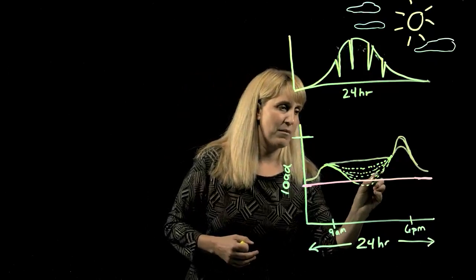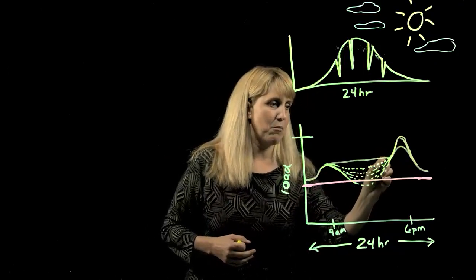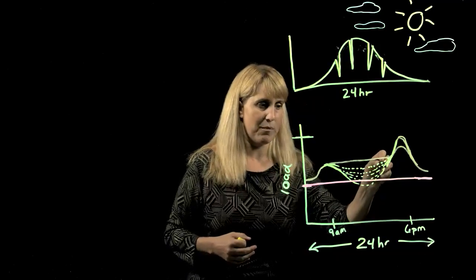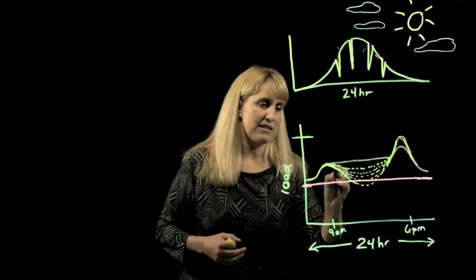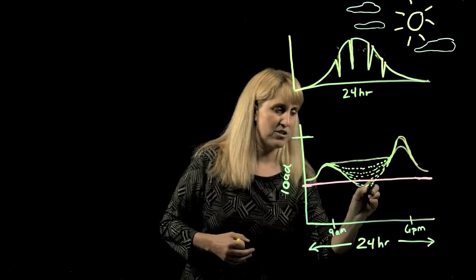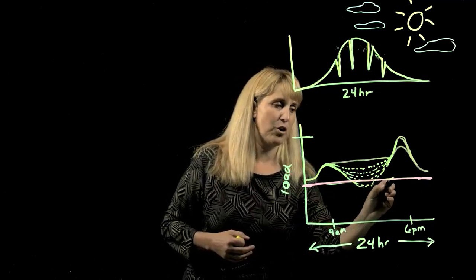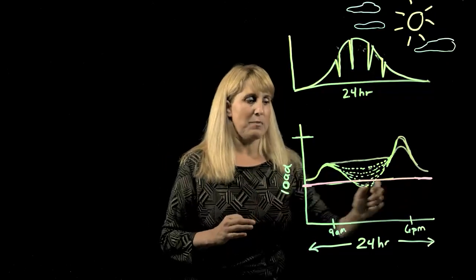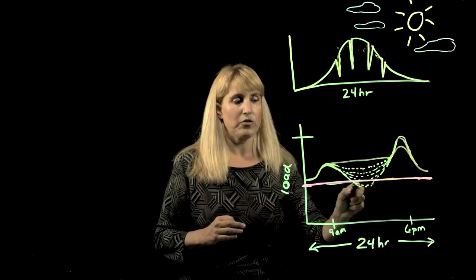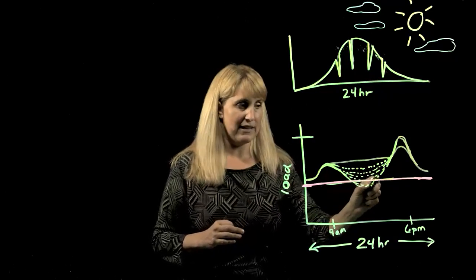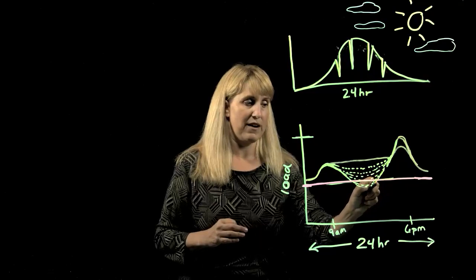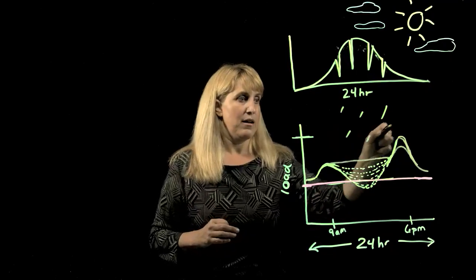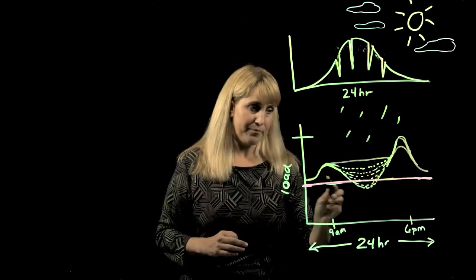And at the same time, you're starting to see a much higher need for ramping of power, like during these evening spikes, for example. So this starts to become challenging, especially once you start to dip down into and below that minimum threshold that's sort of set by your baseload power generation. In this case, you're looking at a situation where you might need to curtail that solar and might not be able to take advantage of that power that's being produced from the sun during that period of time.